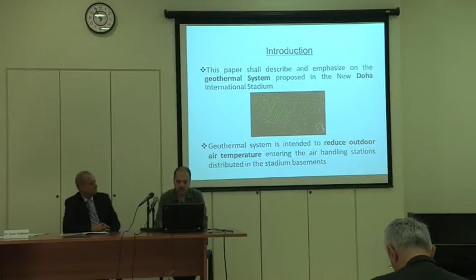As I've said, the project consists of 8 fresh air treatment plants, and each has 200 cubic meters per second air quantity. The available land area that is exploitable for geothermal exchange is the area beneath the parking of that project. So we are limited also in the area that we can use for geo exchange. The outside design conditions that we used for that plant is 46 dry bulb. The wet bulb at that location is 30.5. We intend by this system to lower the outside air by 2 degrees, from 46 to 44. Why just 2 degrees? Because we are limited by the Doha ground temperature, and we are using water as a means to exchange the heat from the air to the ground.